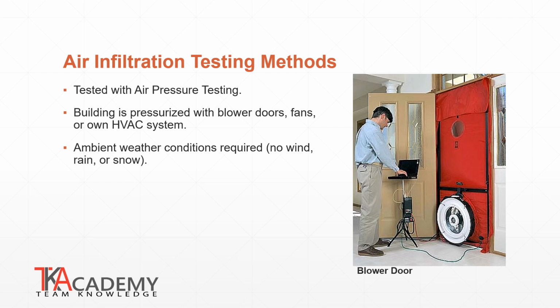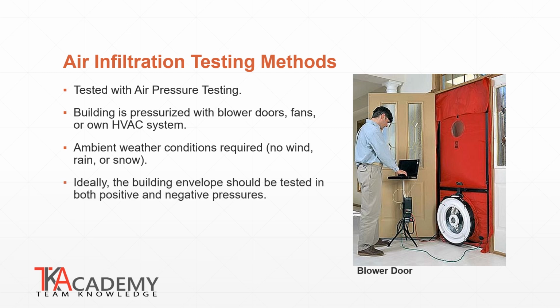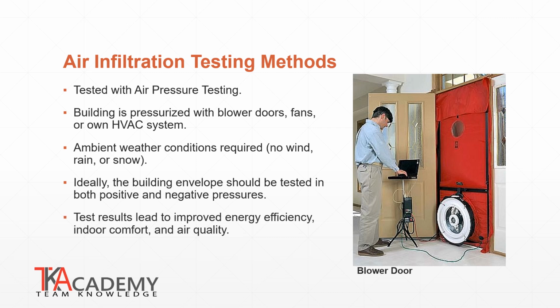The fan is calibrated to measure airflow and the pressure differences accurately. The fan is turned on to pull air out of the building, lowering the indoor air pressure. Higher outside air pressure will then cause air to flow into the building through any unsealed cracks or openings. Technicians use tools like infrared cameras, smoke pencils, or thermal imaging to locate specific areas where air leaks are occurring. These tools help visualize and pinpoint leaks. The rate of air infiltration is measured in cubic feet per minute at a standard reference pressure difference, which is usually 50 pascals. Ideally, the building envelope should be tested in both positive and negative pressures. The results indicate the building's overall air tightness. The data collected is analyzed to identify areas that need sealing to improve energy efficiency, indoor comfort, and air quality.